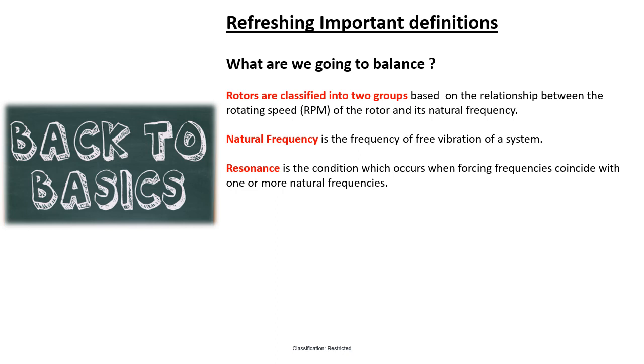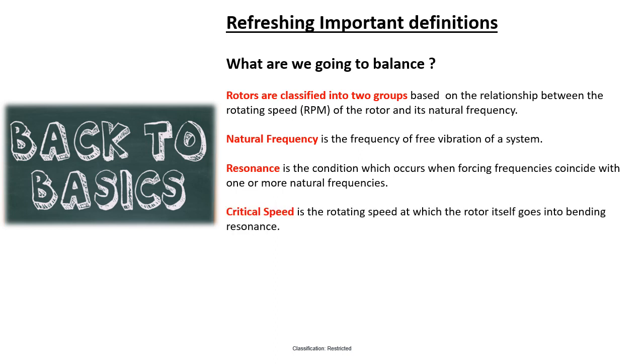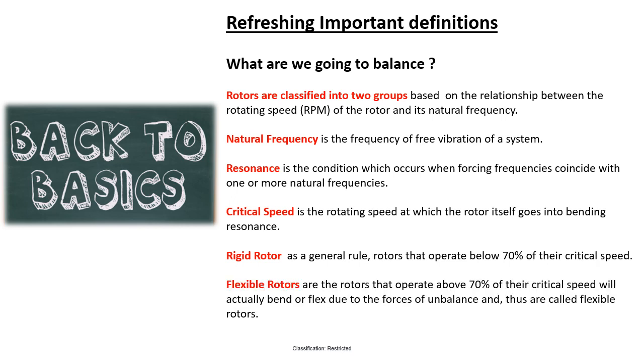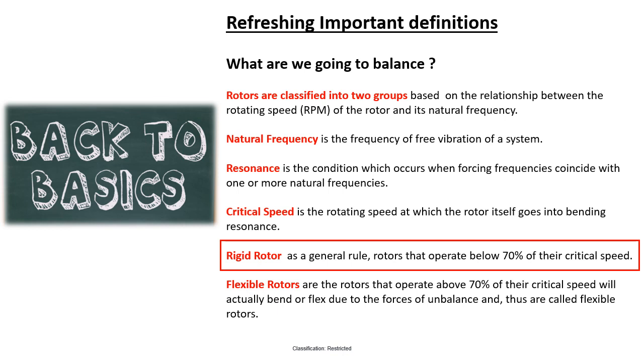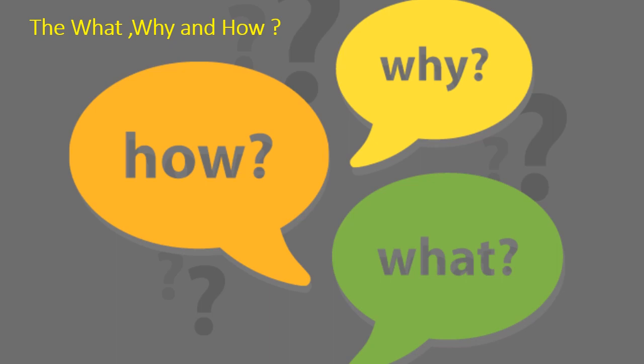Forcing frequencies are typically the frequencies of unbalance, misalignment, looseness, and other defects. Critical speed is a special case of resonance where vibration is caused by rotation of the rotor — it is the rotating speed at which the rotor itself goes into a bending resonance. Rotors operating below 70% of critical speed are called rigid rotors, and those operating above 70% are called flexible rotors. In this video we will talk about rigid rotors only.